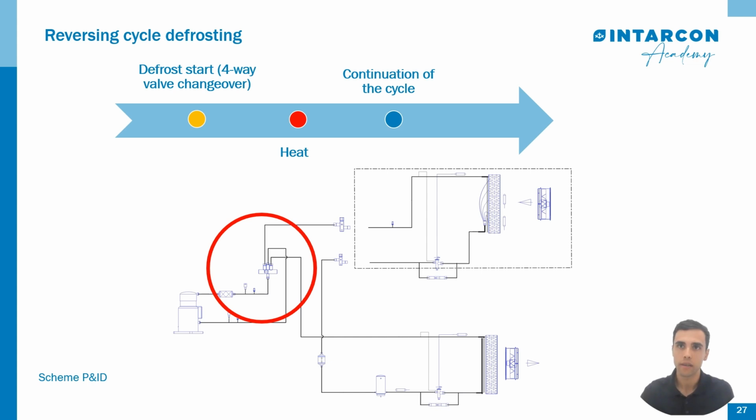Now we look at defrost by cycle reversal, an efficient technique that takes advantage of the reverse functionality of refrigerant systems. This method transforms the evaporator into the condenser and vice versa, similar to reversible heat pumps, to perform defrost quickly and energy efficiently. First, defrost startup.